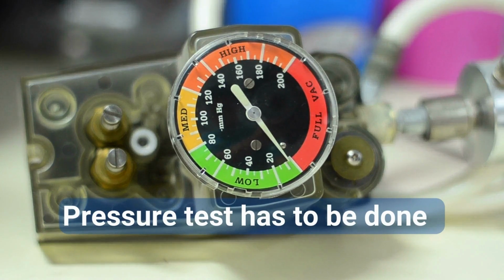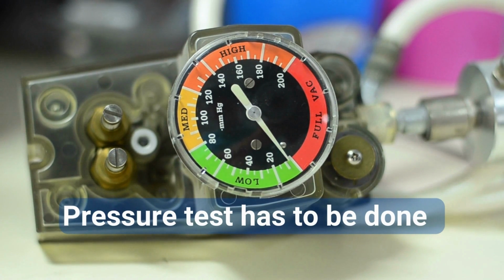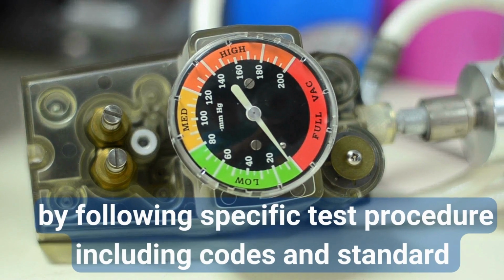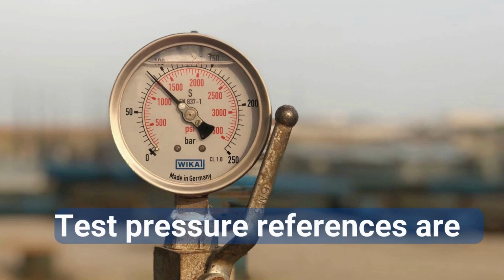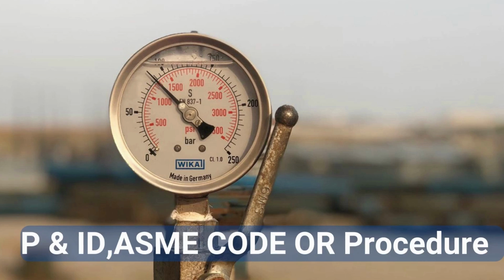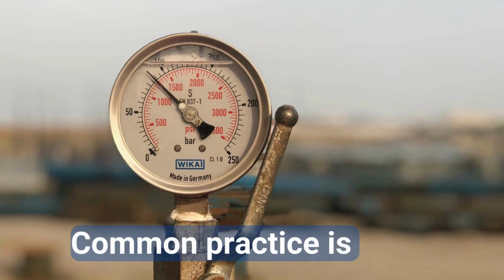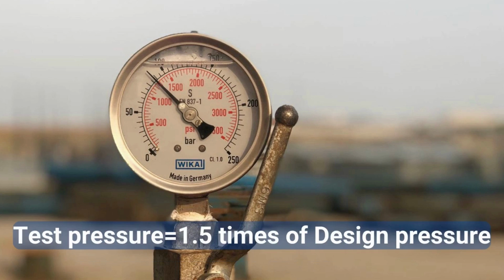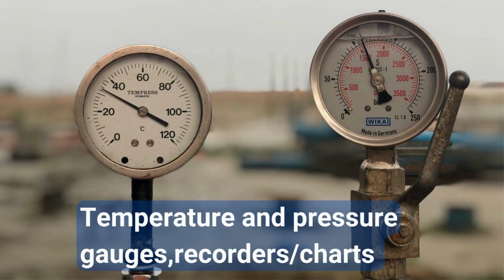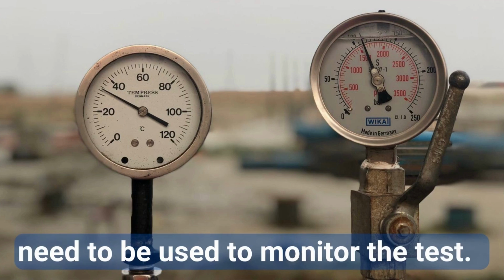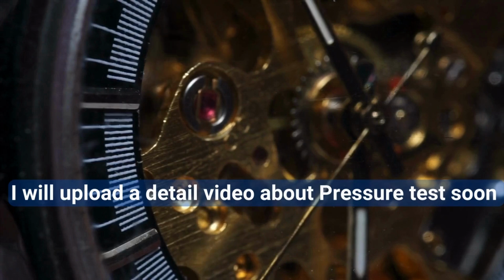Pressure test has to be done by following a specific test procedure, including code, standard, and project specification. Test pressure references are P&ID, ASME code or procedure. Common practice is that test pressure should be 1.5 times the design pressure. Temperature and pressure gauge recorders or charts need to be used to monitor the test. I will upload a detailed video about pressure test soon with all details.